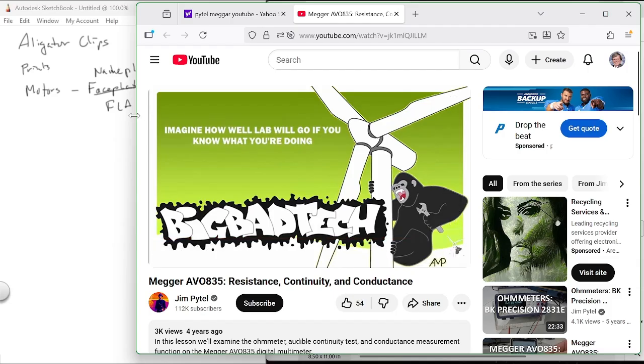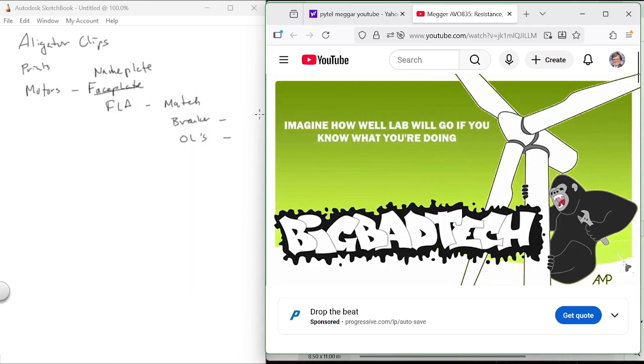Old style meggers were used, and this is illegal, but they were used for something else in addition to checking to see if the motor leads are shorted to the frame or to each other. And they'll test at high voltages. In other words, when you use a DMM, you're checking at the battery voltage, which is the 9 volts in the battery, which is not high enough to break down any shorts. 500 is. If you put 500 volts, it will find any weakness in the wire or any weakness in the insulation, whereas 9 volts won't. That's why they use meggers.